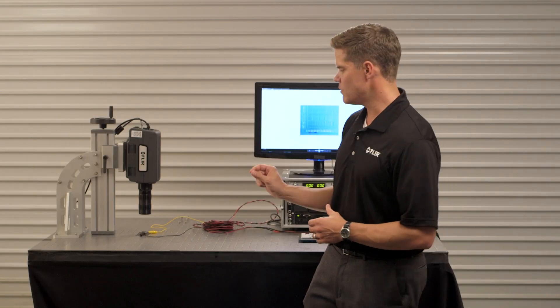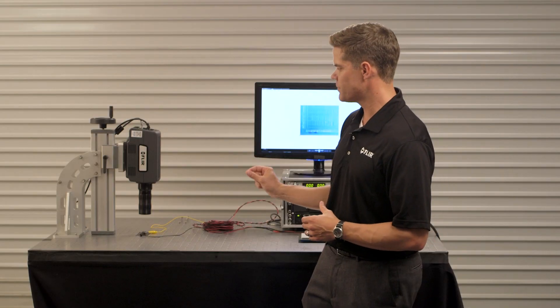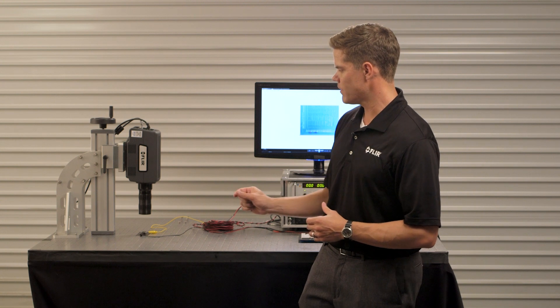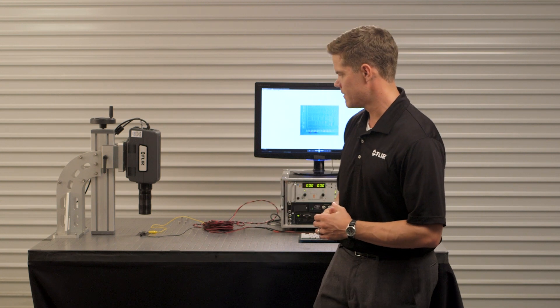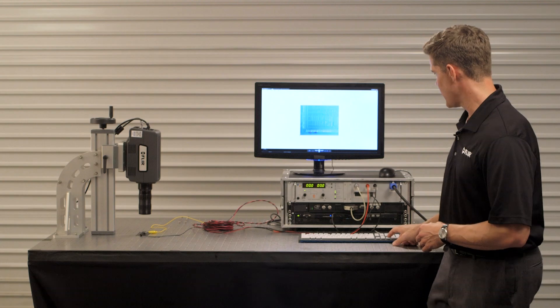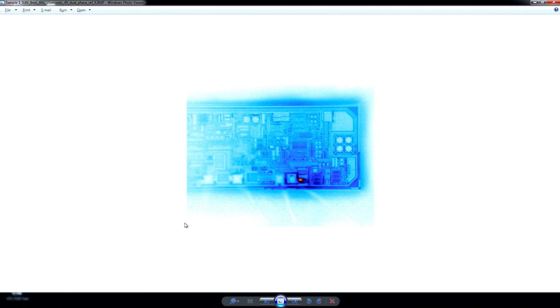So we can see really subtle temperature differences as well as very small spot sizes. And here's some sample imagery that we have. You can see some blown diodes here in the bottom of the imagery and again in a different color palette. Here's another failed diode on a chip, and this is all done using a 4x or 1x close-up lens, so we're talking about a few micron per pixel spot sizes.